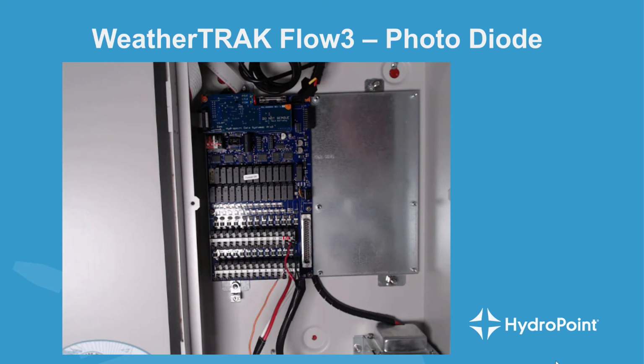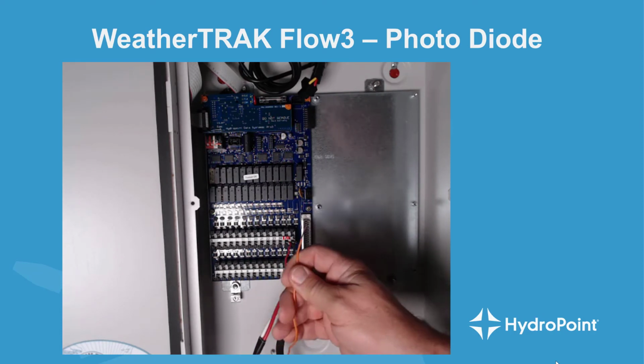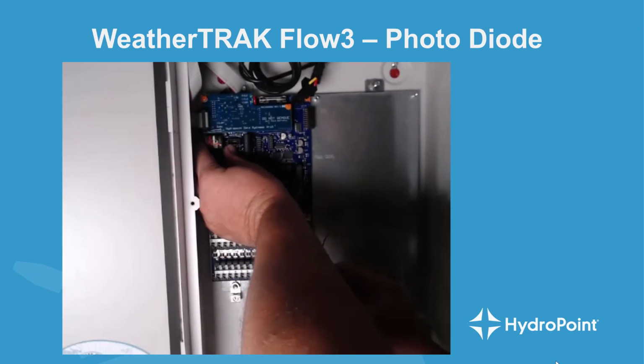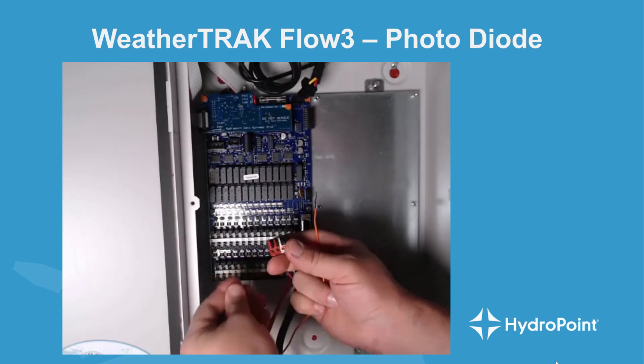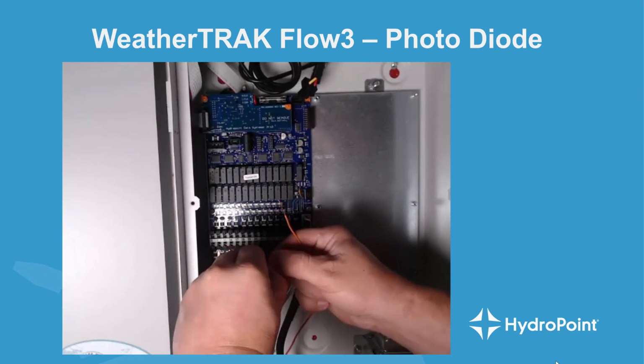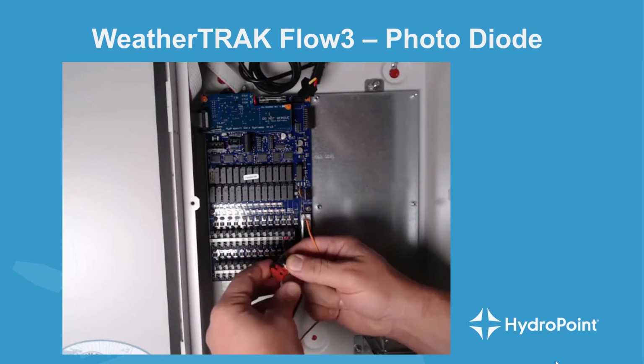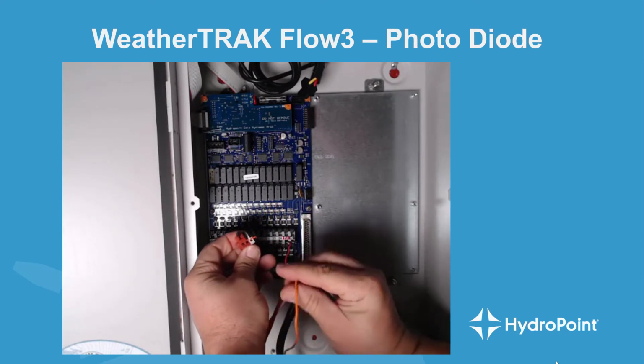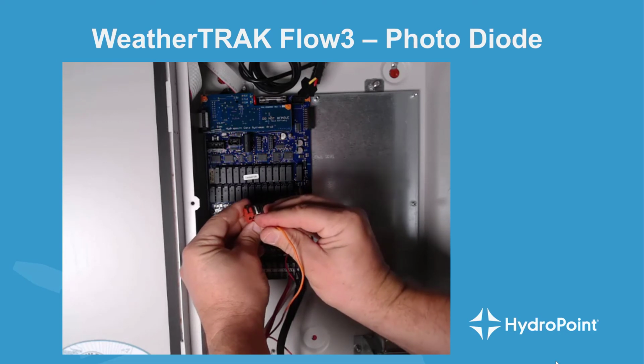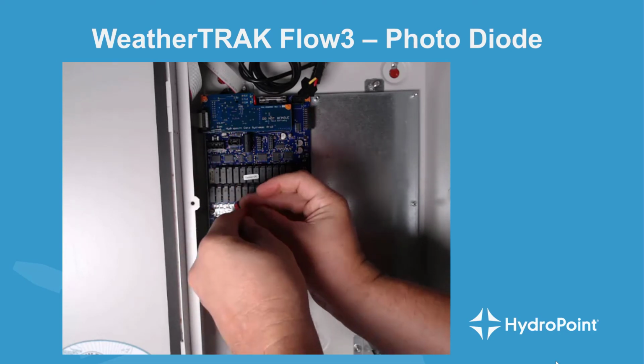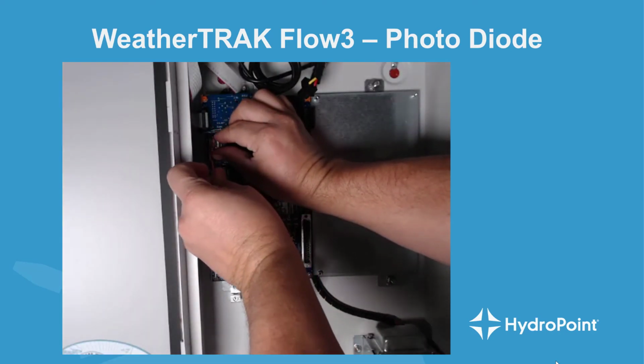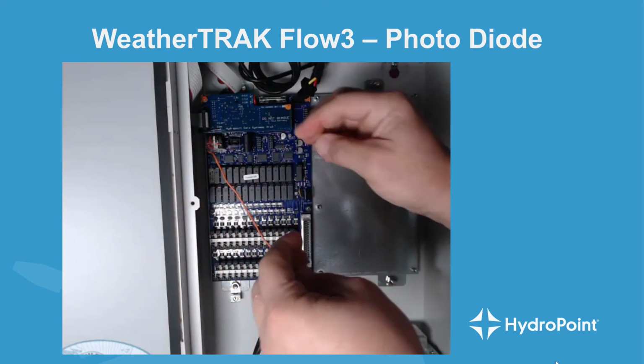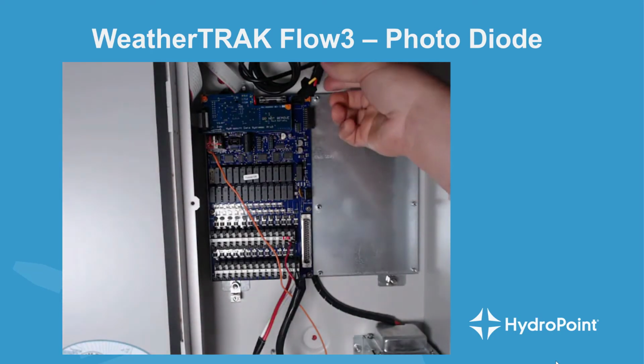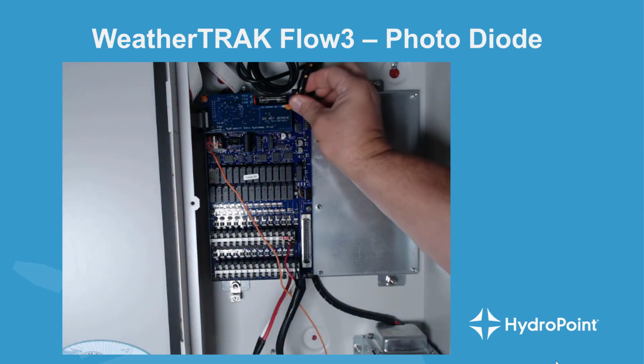The last wire we need to connect is the 24 volt power cord, and that plugs into the rain sensor. So to plug that in, I find my 24 volt power wire and I pull the rain sensor adapter out, and I will plug the 24 volt wire into the first terminal on the rain sensor port. The 24 volt power goes into this port right here. We lock that down. We plug that back into the board, and we're ready to power up the controller again by plugging in the wire from the transformer.